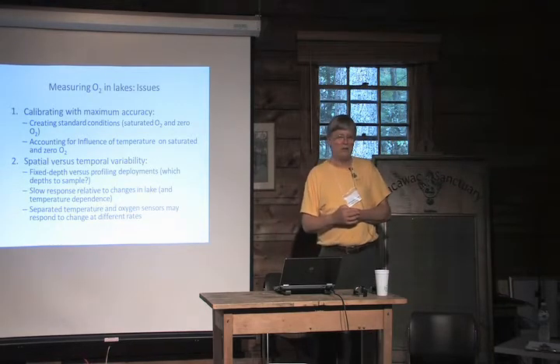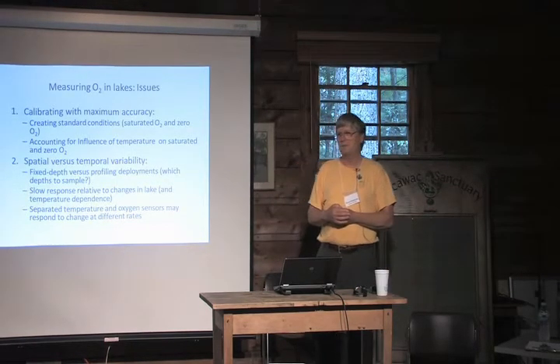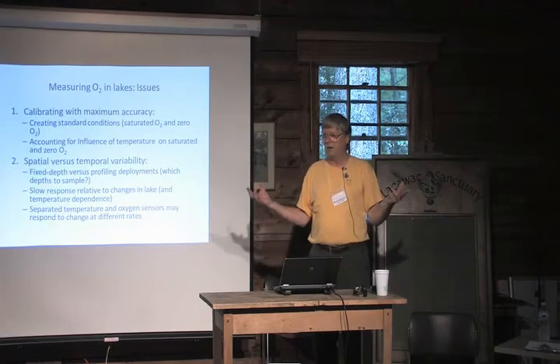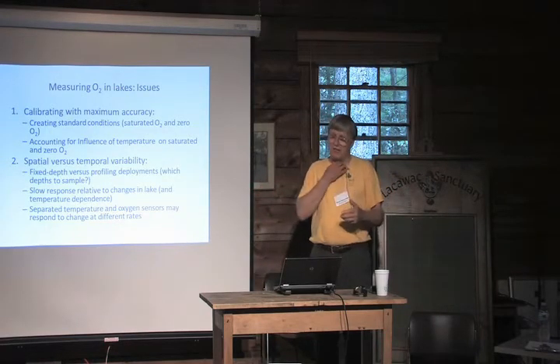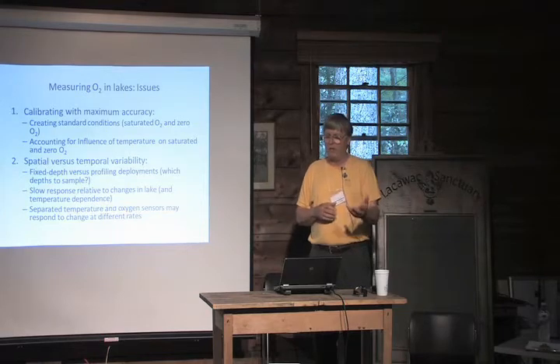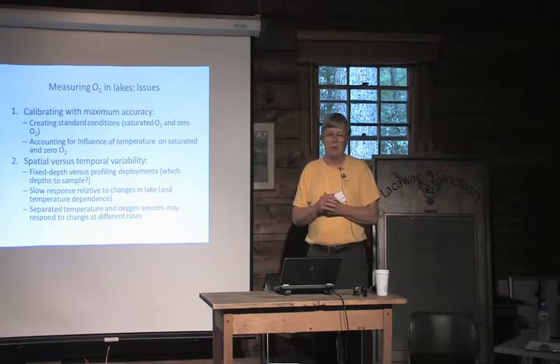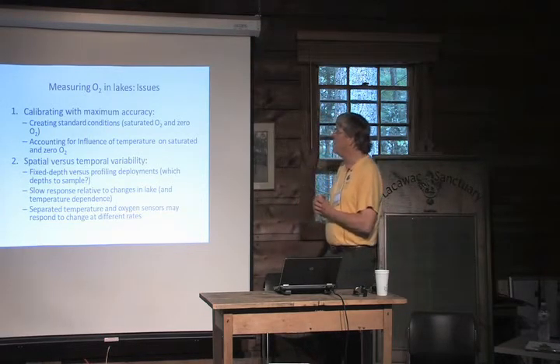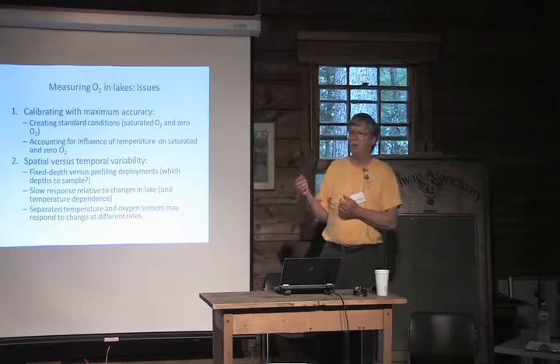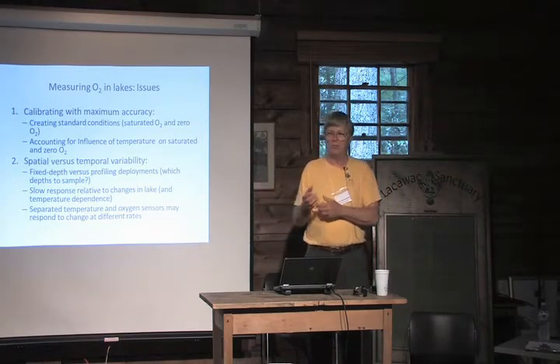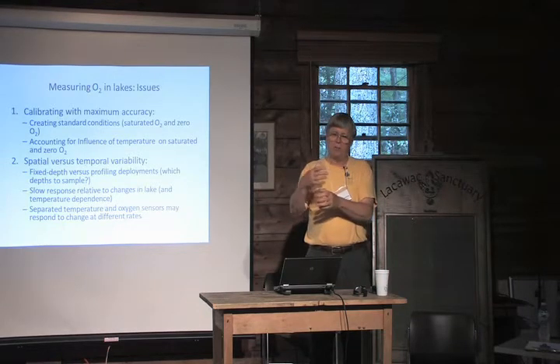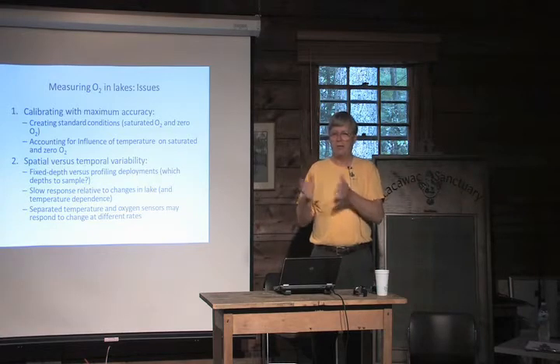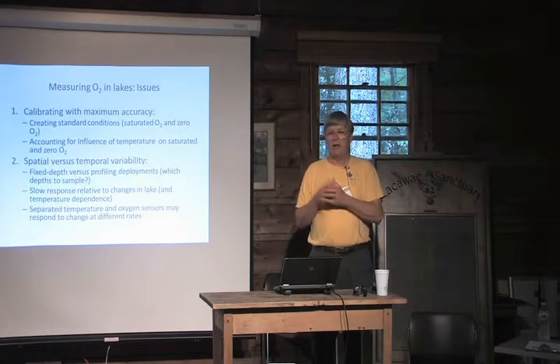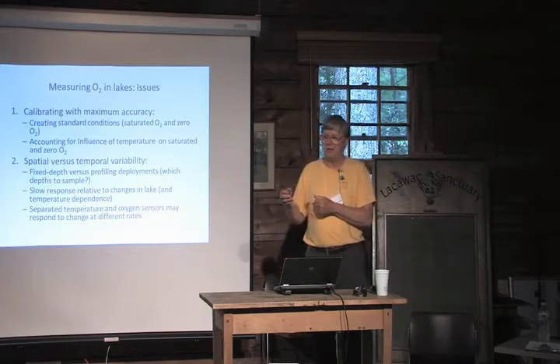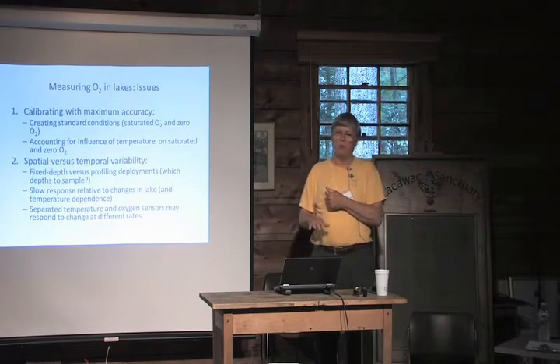Probably the gold standard is an oxygen-air mixture, either a gas mixer with pure gases or commercial mixes that you perfuse into an air chamber, and you can see the response. Most people don't have access to that kind of tool. The most widely used, say with YSI oxygen probes, is you put the sensor into a humid chamber, so it's got air in it and water vapor, and you let it stabilize at a constant temperature, and you can calculate the equilibrium value because the air partial pressure is the same as in the water.